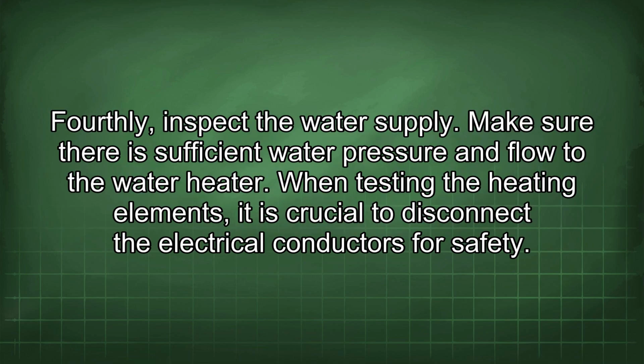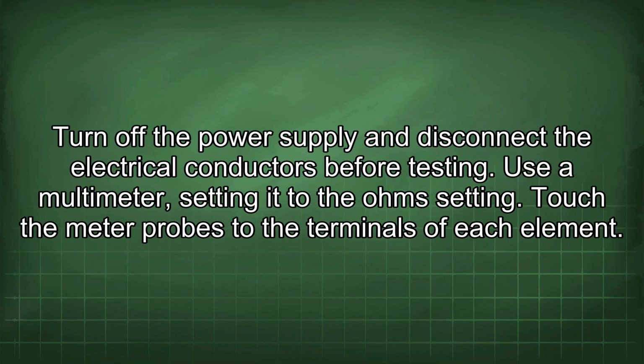Fourthly, inspect the water supply. Make sure there is sufficient water pressure and flow to the water heater. When testing the heating elements, it is crucial to disconnect the electrical conductors for safety. Turn off the power supply and disconnect the electrical conductors before testing.